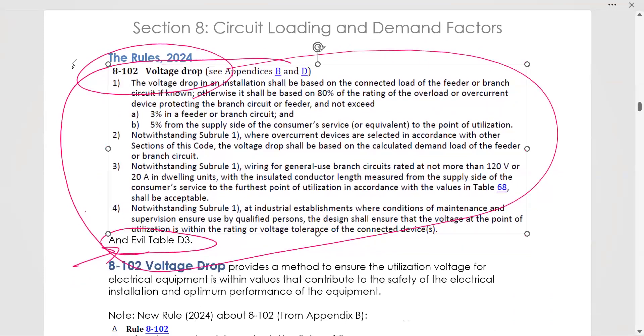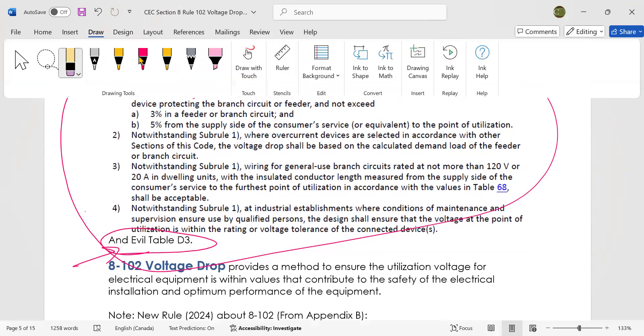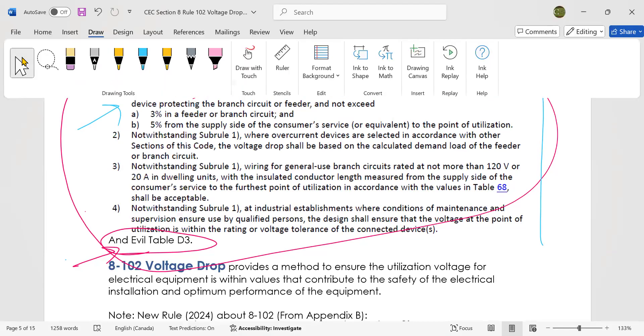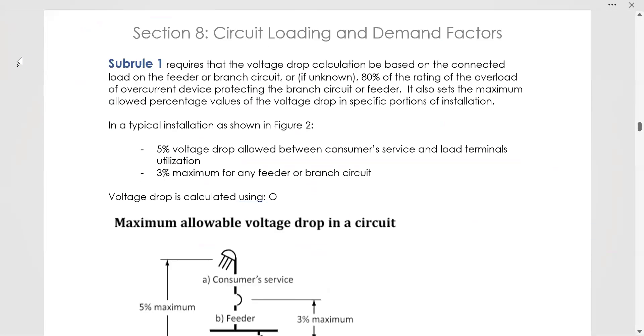So let's talk about what it says in 8.102 voltage drop. Rule one, I mean, subsection one, subsection one here, let's get another color here. Subsection one just says that the voltage drop can't be more than 5% from the source to the load. And it can't be more than 3% in a feeder or branch circuit. All right, so I'll show you where that is. I mean, I'll show you a diagram of that.